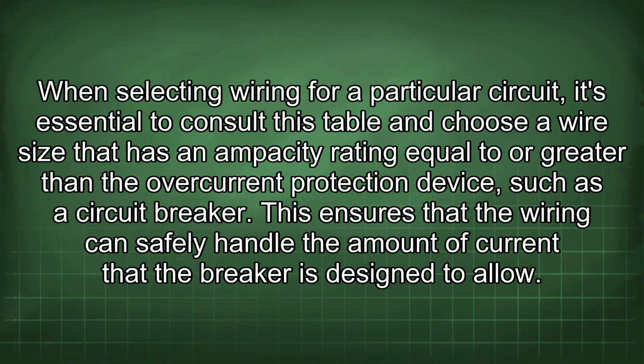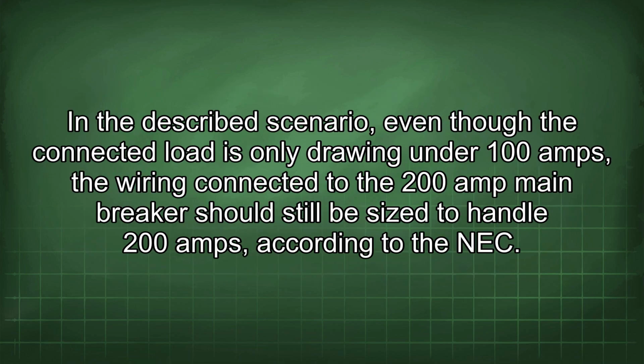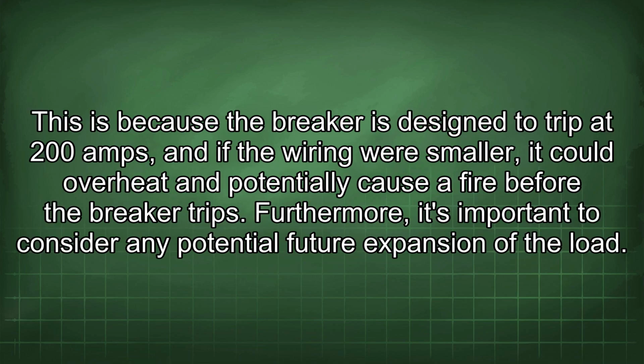When selecting wiring for a particular circuit, it's essential to consult this table and choose a wire size that has an ampacity rating equal to or greater than the overcurrent protection device, such as a circuit breaker. This ensures that the wiring can safely handle the amount of current that the breaker is designed to allow. In the described scenario, even though the connected load is only drawing under 100 amps, the wiring connected to the 200 amp main breaker should still be sized to handle 200 amps according to the NEC. This is because the breaker is designed to trip at 200 amps, and if the wiring were smaller, it could overheat and potentially cause a fire before the breaker trips.